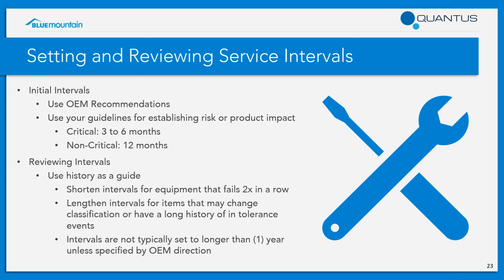And then reviewing service intervals. Why would we want or need to do this? Well, the historical data of your equipment holds a significant amount of value for a variety of reasons. One basic example is the performance of pass-fail results. This is going to allow you to track the performance of your equipment over time and can really help you identify trends, anomalies, and patterns within that instrument. In the category of service intervals, we're typically going to monitor them to see when we need to shorten or lengthen them depending on the performance of the device. And in general, what we recommend is if an instrument is going to fail calibration 2 or 3 times in a row, we're going to look to reduce that interval typically by half. And then we're going to perform calibration at that halved interval for 2 or 3 more times.